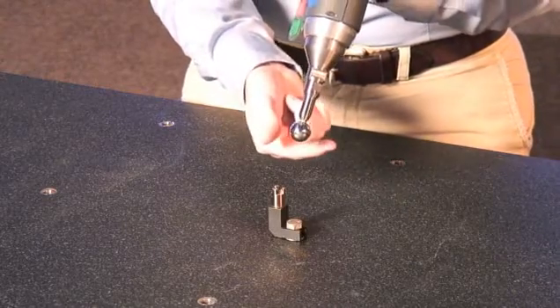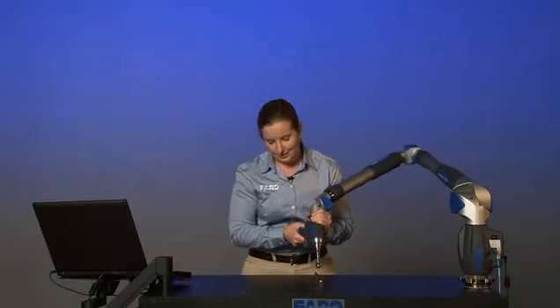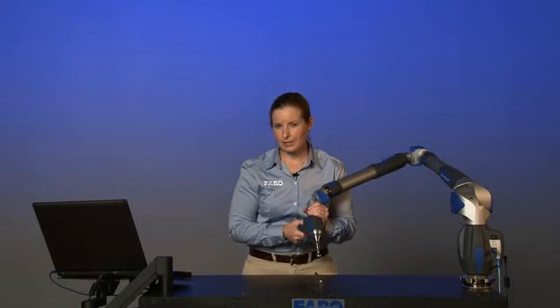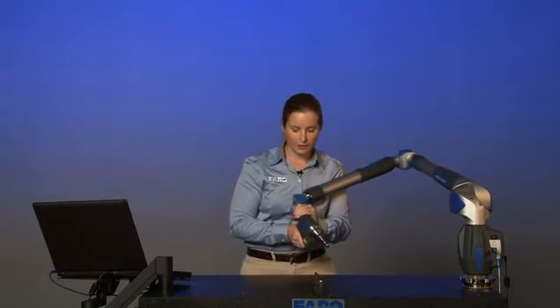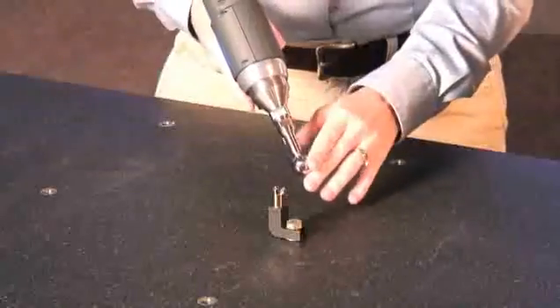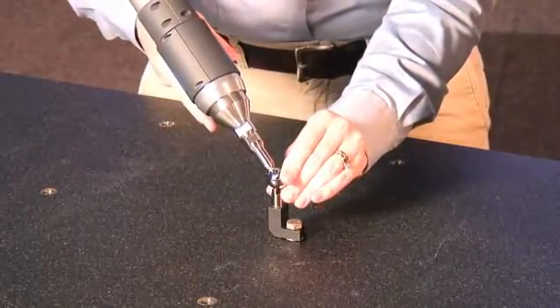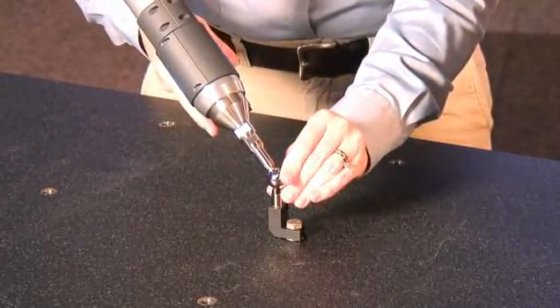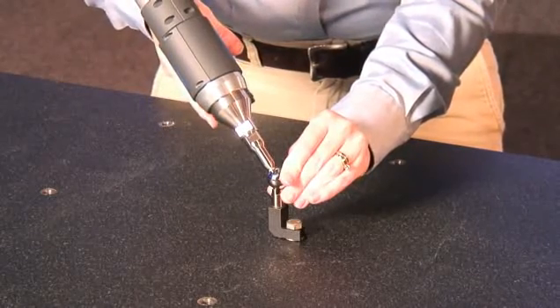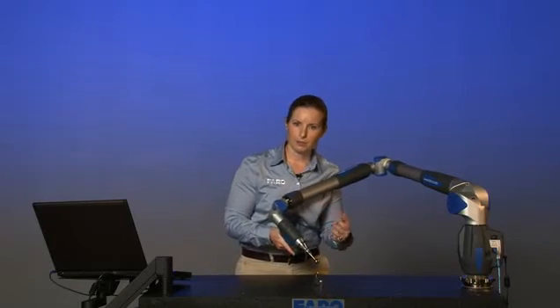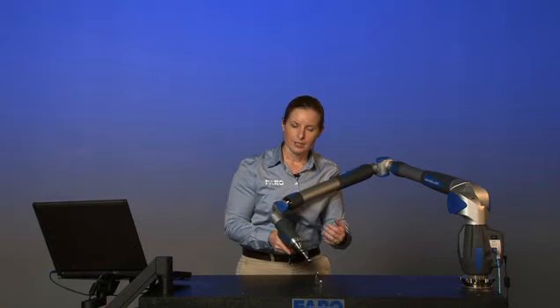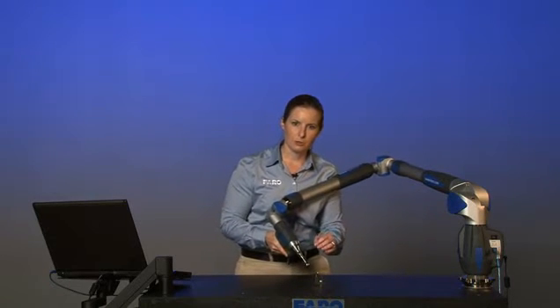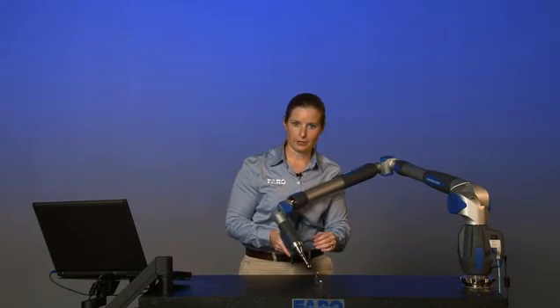We're going to rest the probe inside the cone and take points sweeping in each of the three cuts. Because this is a large diameter ball, it doesn't sit inside the cone very easily. It has a tendency to slip out. Because of that, you can use your hand to make sure you keep the ball in that location as you're taking points. We're also going to modify our probe calibration method slightly so that we can make sure we get a stable pivot of the ball as we're calibrating.